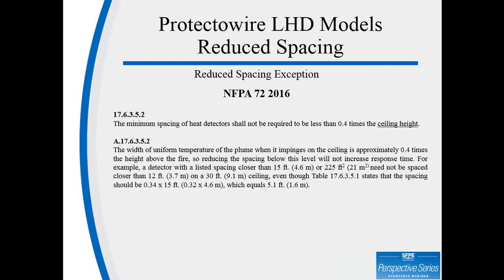Protectowire LHD models and reduced spacing. Most of you will have noticed that on the previous slide, the chart only went to 30 feet. But there are many buildings and ceilings out there that are much higher than 30 feet. And NFPA 72 put in this clause a few years ago, and it deals with ceiling height. 17.6.3.5.2 states the minimum spacing of heat detectors shall not be required to be less than 0.4 times the ceiling height. If you took a 100-foot building and a 50-foot listed spacing, you would reduce it down to 40 feet on centers. And that 40 feet is 0.4 of the 100, not of the 50-foot spacing.